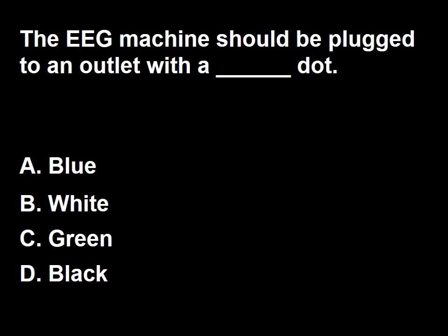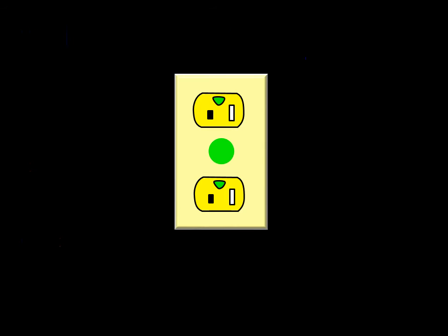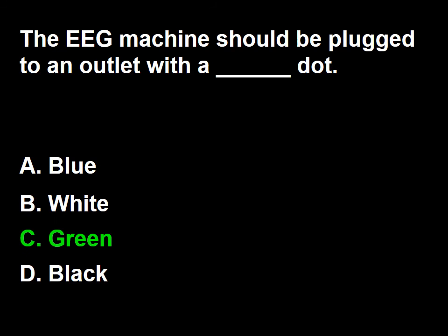The EEG machine should be plugged to an outlet with a dot of which color? A: blue, B: white, C: green, D: black. The EEG machine should be plugged to an outlet with a green dot. The green dot in a receptacle indicates good working condition and a high degree of safety. So the answer is C.